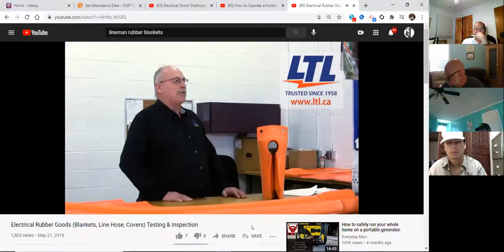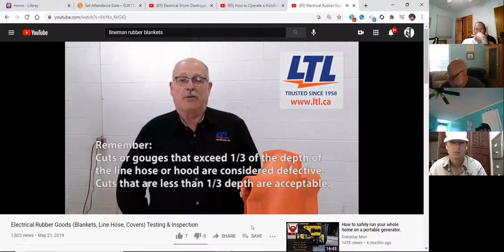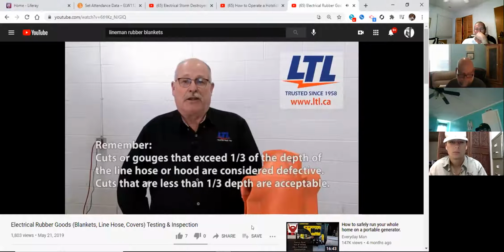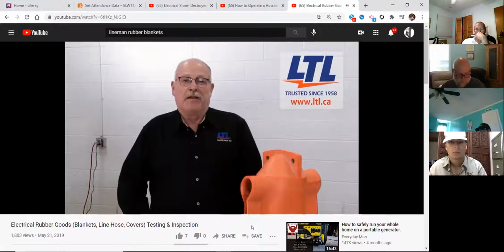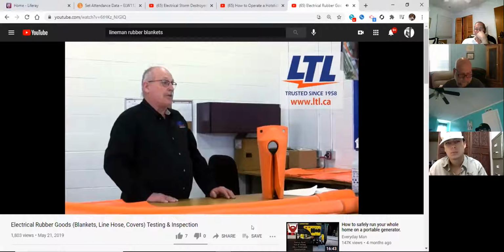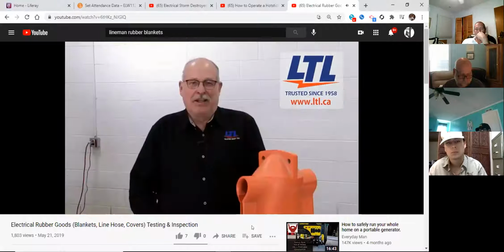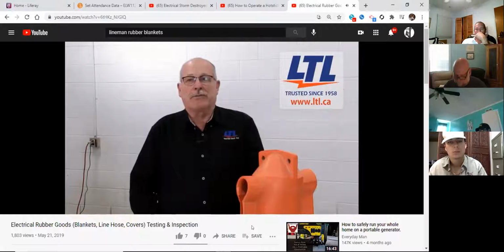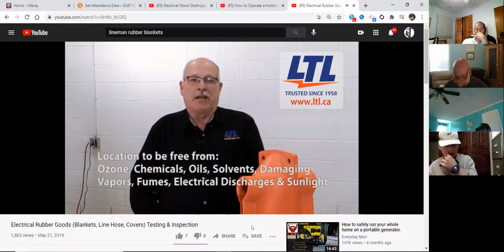Blankets, line hose, and covers are to be inspected visually for defects before use and at other times if there's reason to suspect any damage, using the same inspection process. Be sure to remove any oil, grease, or other damaging substance as soon as possible, using only a mild detergent if necessary. It's important that blankets, line hose, and covers are stored in a bag, box, container, or compartment designed specially for them, in a location that is cool, dark, and as dry as possible, free from ozone, chemicals, oils, and away from electrical discharges and sunlight.